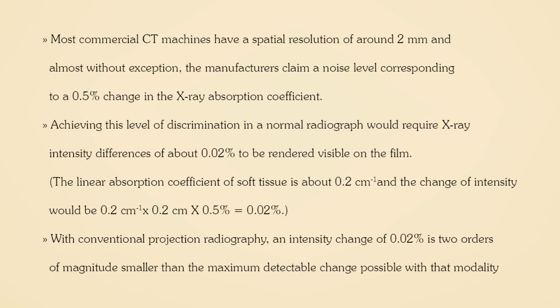Most commercial CT machines have a spatial resolution of around 2 millimeters, and almost without exception the manufacturers claim a noise level corresponding to a 0.5% change in the X-ray absorption coefficient.